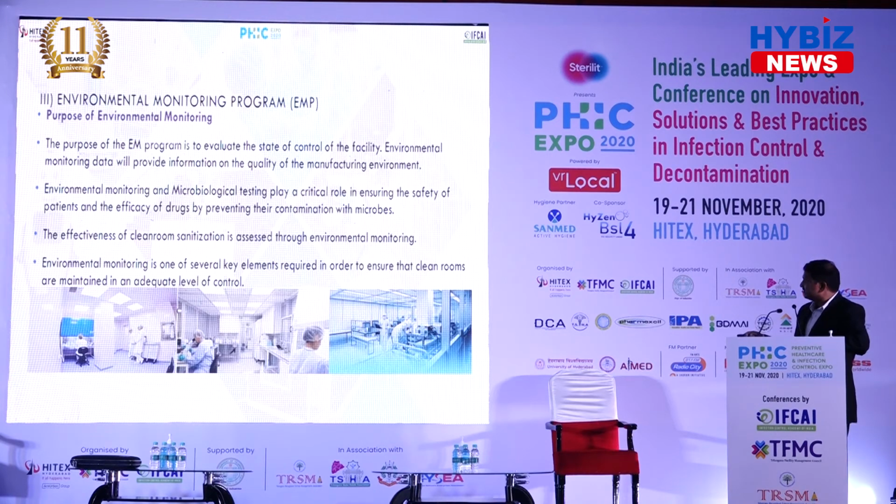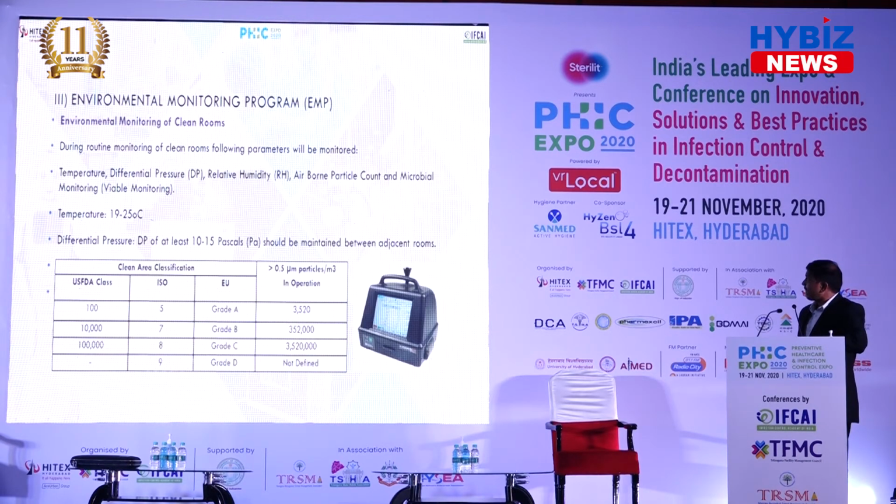These are some of the clean room areas displayed in these pictures. During routine monitoring of a clean room, some parameters are monitored, among them temperature, differential pressure, airborne particulate count, relative humidity, and viable monitoring, which is performed as a routine process at defined frequencies.